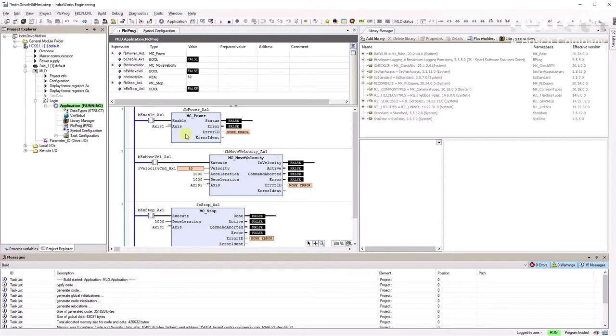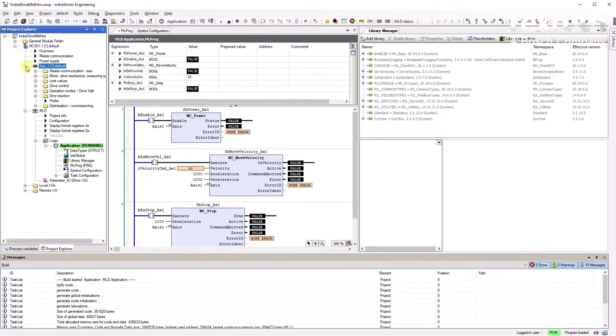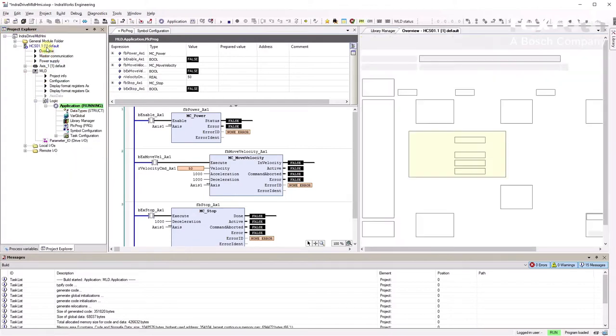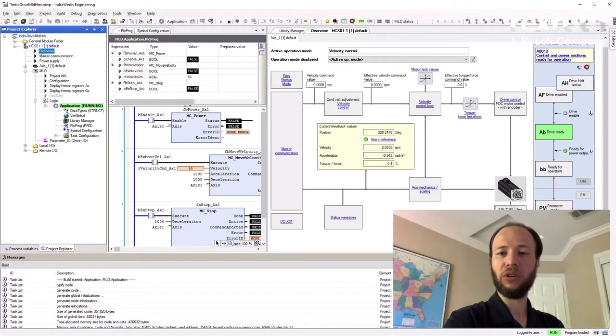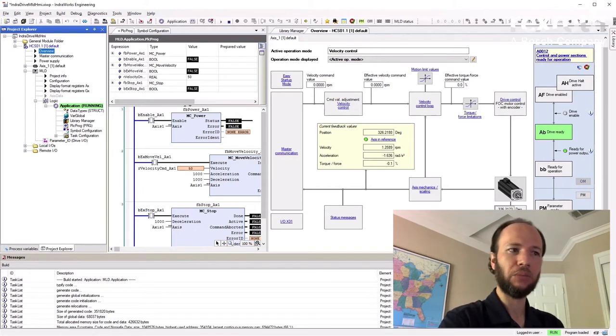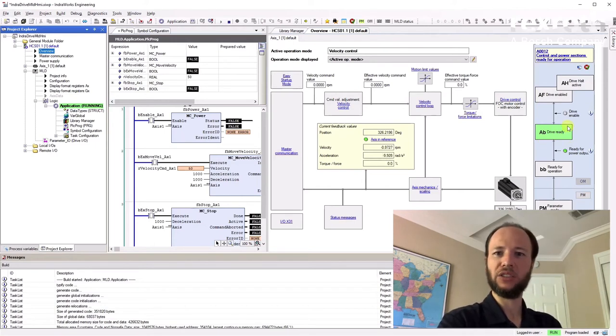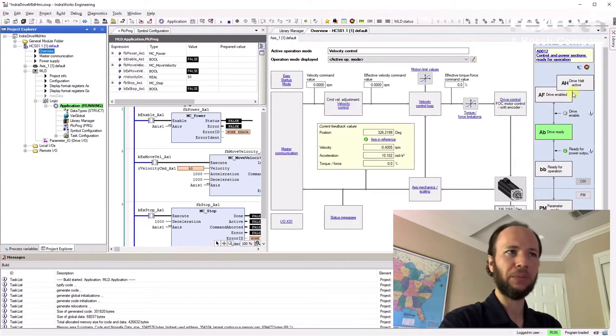Double-click on the PLC to see the online view. Let me bring up the drive overview. Double-click the overview — my motor is in reference, meaning the drive knows exactly where the motor is located. My drive is in AB state, which means the bus is loaded, ready to enable, and waiting for an enable command. Once I enable it you should see AH or AF become active.